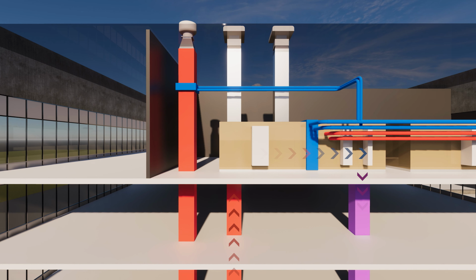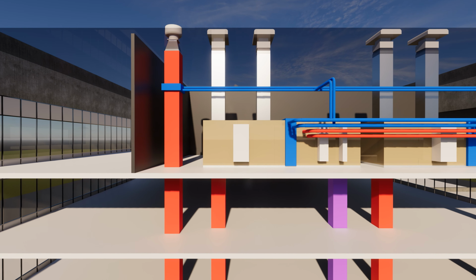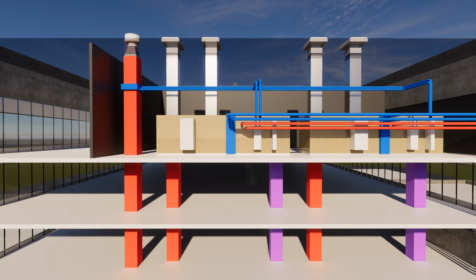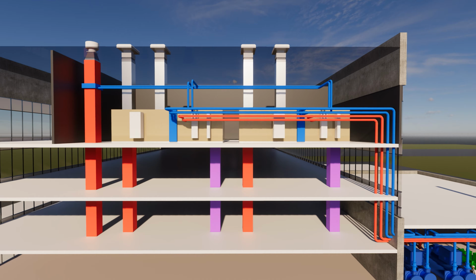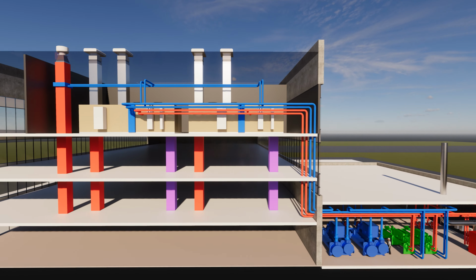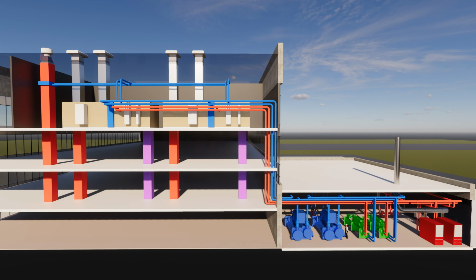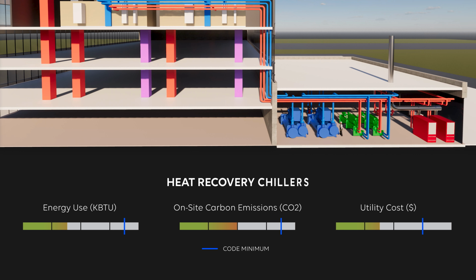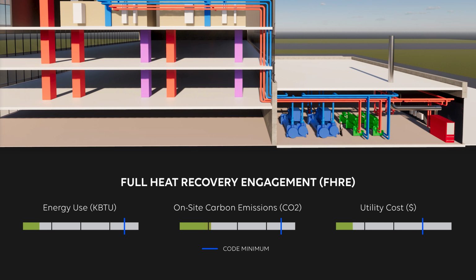There are other coils that can be used in the building to capture waste heat, such as exhaust air streams. All of these coils tie into the same chilled water loop, which has captured heat from the air streams, and as a result, the water is warmer. Now we can follow the warmer water as it returns to the central plant. Using the heat recovery chillers in the plant, the heat is removed from the chilled water loop through the vapor compression cycle and transferred to the hot water loop. This reduces the load on the boilers and saves even more utility costs, carbon emissions, and energy.